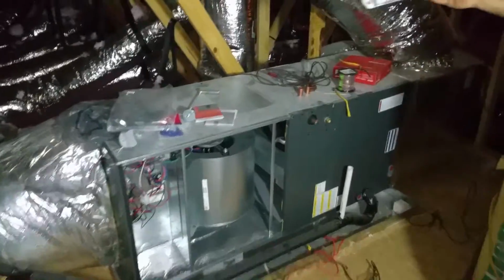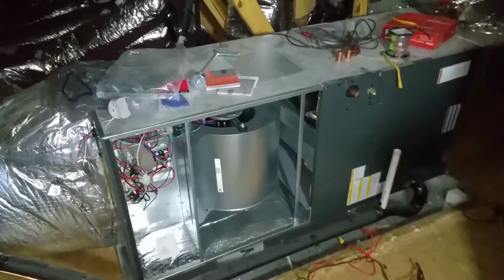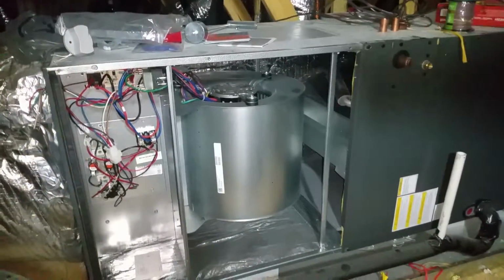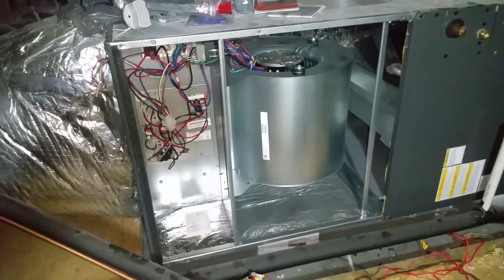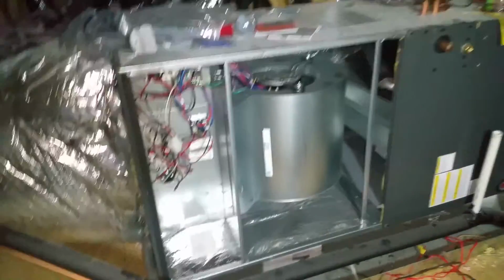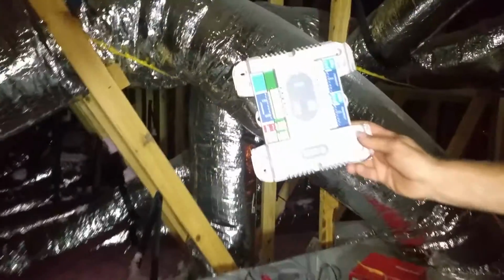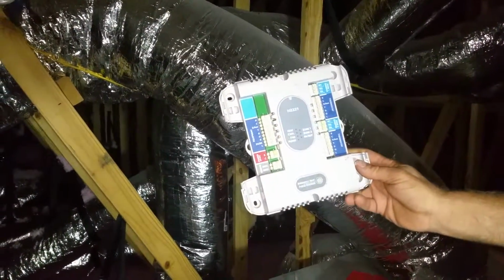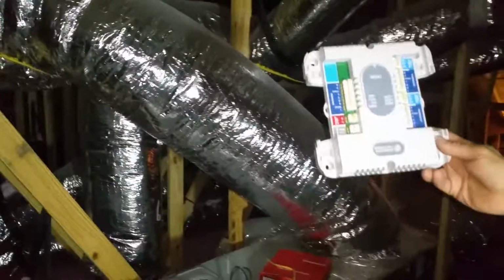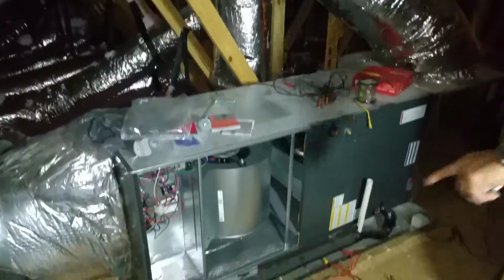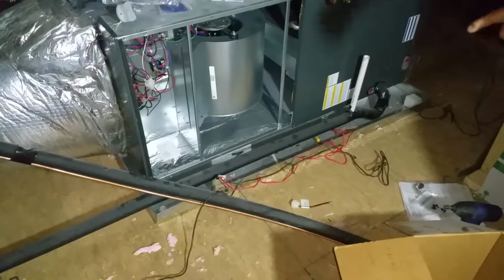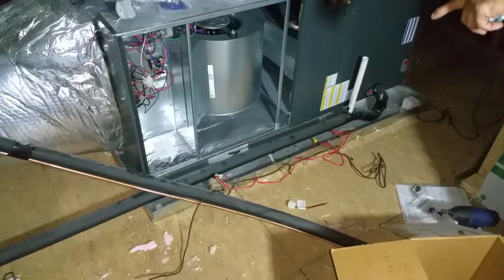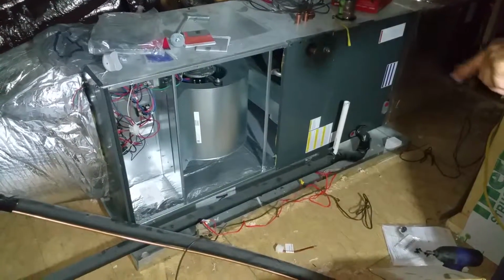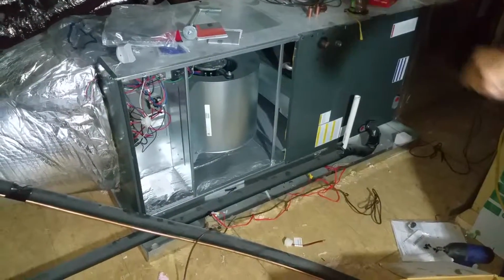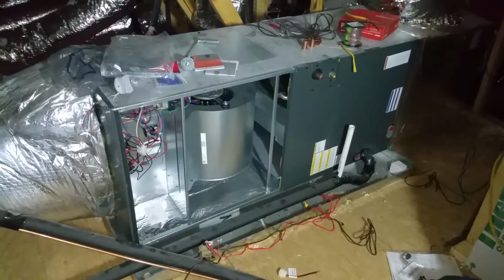So what do we got here, Don? We have a matching 14 SEER Goodman air handler for the condenser outside. We have installed a 10 kW electric strip backup heater to supplement the heat pump on the cold days. I'm holding in my hand a zone panel because we're creating 2 zones. First floor and the bonus room will be on their own zone. And we have a metal secondary pan under the air handler. We have connected a float switch on the bottom for safety. So in case the pan overflows with water, the float switch will shut the unit off. And that's that white pipe that's outside where all the drainage goes, okay?